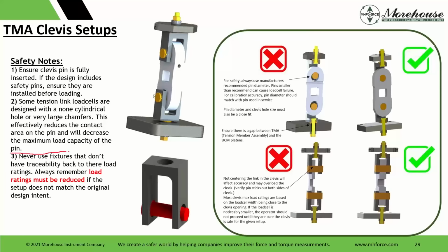This is a big one, because this is where we failed on that other drawing, or in that other slide, right? It did not match. We used a smaller pin, it did not match, and there was a problem. So in addition to that, you can see some other things over here. Not centering the link in the clevis will affect accuracy and may overload the clevis. Verify the pin sticks out both sides of the clevis. Most clevis max load ratings are based on the load cell width being close to the clevis opening. If the load cell is noticeably smaller, the operator should not proceed until they are sure the clevis is safe for the given setup.